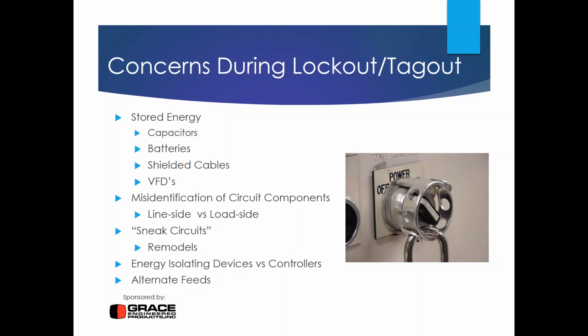Misidentification of circuit components can be a very significant problem, especially with respect to identifying what is line side and what is load side. Please do not assume that devices are top fed all the time. There are many situations, and a wind turbine is one, where you may find breakers that are bottom fed. So make sure that when you're doing your testing or when you're installing a device like a PESD, that you're clear on what is the source and what is the load side, and it may not be the top set of contact points. Sneak circuits can exist anytime there's a junction box. Basically, a significant remodel where additional walls have been added, for example, could be a problem. We have a circuit that comes from a source that we didn't know was there. So sneak circuits represent a problem, especially when you do remodels inside of buildings.